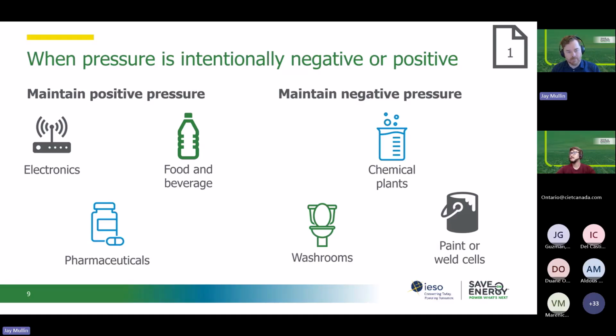Like ISO 14644, it has 9 levels of clean rooms, and the recommended pressure differential to prevent contaminants from one level getting into the next is about 5 to 20 pascals, and people will typically design for around 10. So that's 0.02 to 0.08 inches of water column differential. So we're not talking about a huge pressure differential. And sometimes you might be getting even more than that by accident in your facilities.